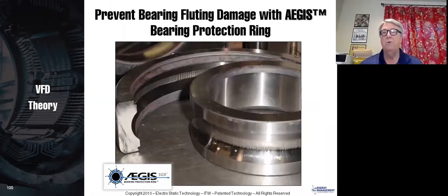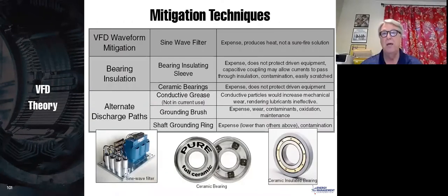Well, how can you protect against something like this happening? First of all, if you send your motor in for refurbishment, rewinding, they need to cut that bearing and do an inspection. Here's various ways of protecting that. The first thing that seems to make a lot of sense to me is an insulated bearing. Now, this bearing over here is an insulated bearing. It's got an insulated coating around the outside of the bearing, or you could coat the frame there where the bearing goes into the frame.